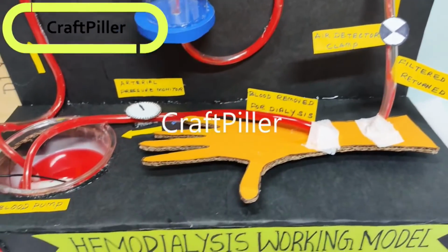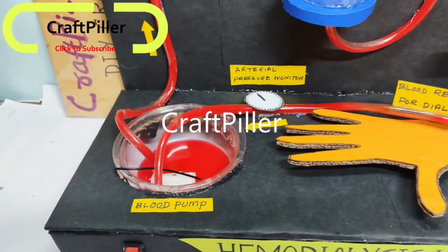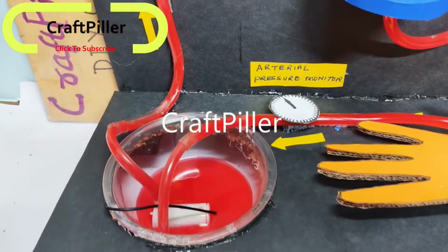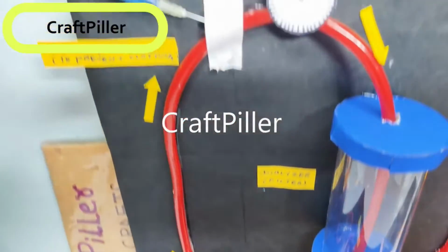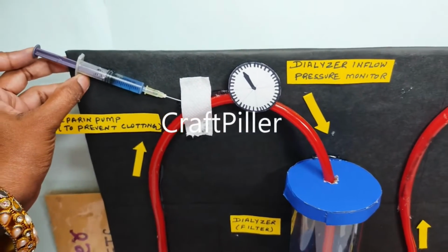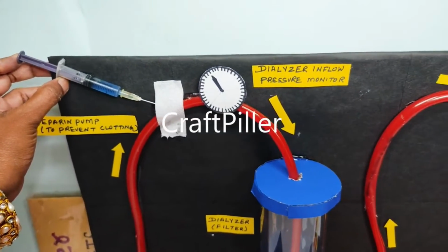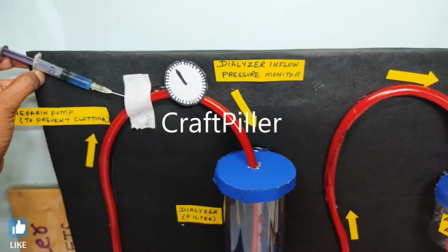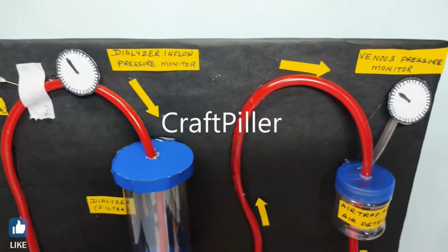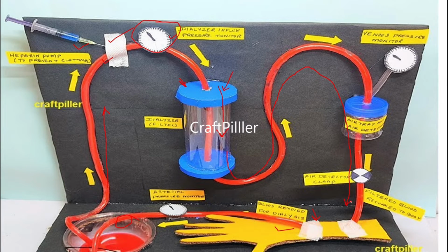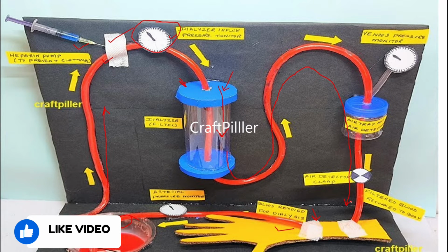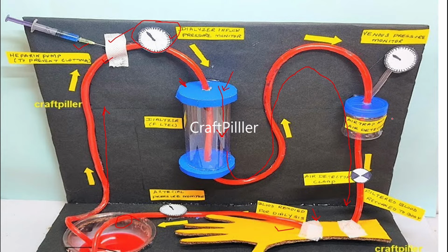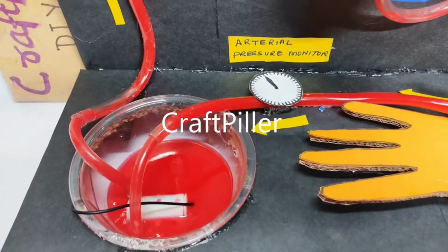During sending the blood back to the human body, we should also check if there is any air trapped in the blood after the dialyzer. We have to ensure there is none, otherwise this air gets added into the blood and sent back to the human body, which is not good. Because of that, we have included an air trap detector that detects and removes those air bubbles from the blood before it is sent back to the human body.